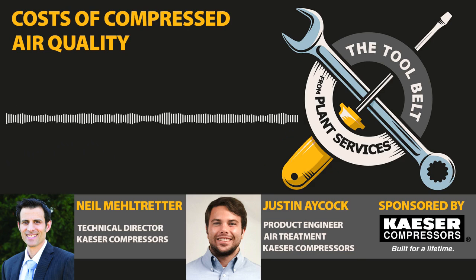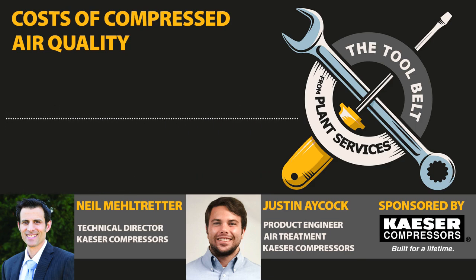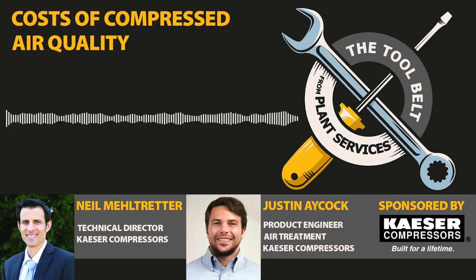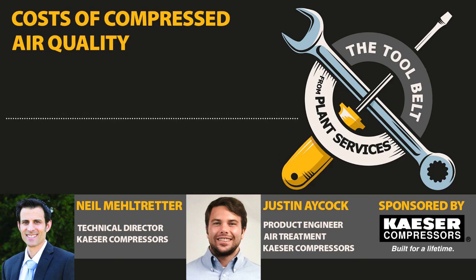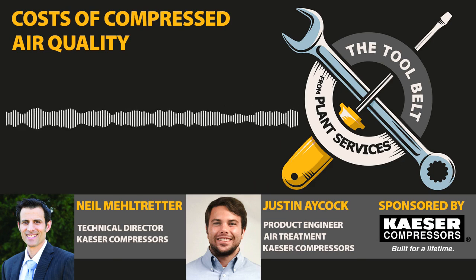So a typical air compressor is 80 to 125 psi operating, and you can buy compressors that have different air ends and so on, and you can run at higher pressures for different applications. But the higher you run, the more energy that compressor is going to expend, and the closer you're running to its utilization rate or service factor. Those compressors should be able to run there, but nonetheless, you're going to be paying more for it. At higher pressures, you will also have higher flows.